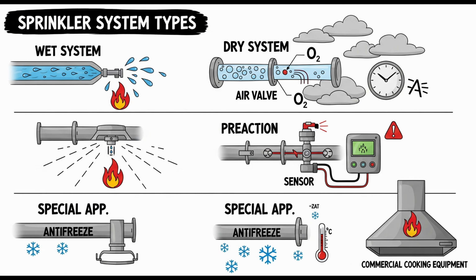Right. And additional sprinklers or nozzles are also needed to protect the cooking equipment surfaces themselves, unless, as I mentioned, the hoods covering that equipment already contain a listed fire extinguishing system. These are typically wet chemical systems designed specifically for kitchen hazards, often meeting UL 300 standards. So if the hood itself has its own built-in listed suppression system, like those nozzles you see under hoods, then that system is considered to protect the equipment under the hood, and you don't necessarily need additional sprinklers from the building system spraying directly onto that equipment.